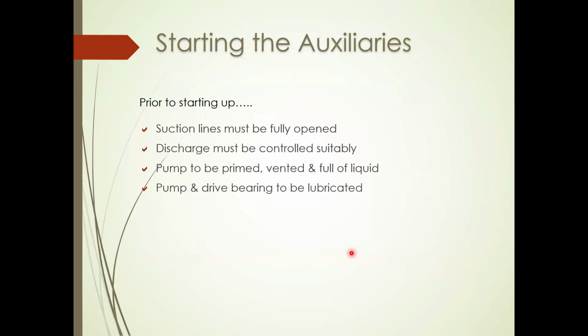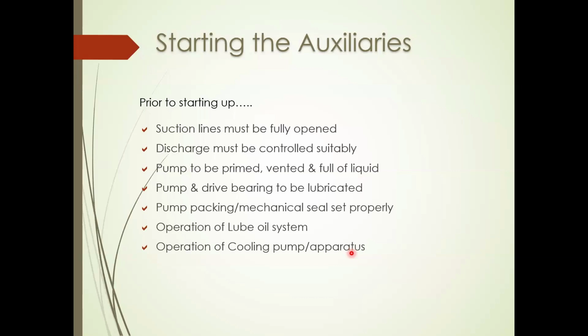And of course, as I've told you, in the case of the BFP, the boiler feed pump, the pump and drive bearings have to be lubricated. The lubrication oil system has to run. Prior to starting, the mechanical seals have to be set properly. And of course, the cooling water pumps and cooling apparatus have to work prior to the startup. Otherwise, your windings and your lubrication oil get heated up very quickly and it will do more damage than the startup. And of course, achieve water chemistry. If there is a requirement, you have to achieve the water chemistry. Maybe sometimes you have to start the filters beforehand.